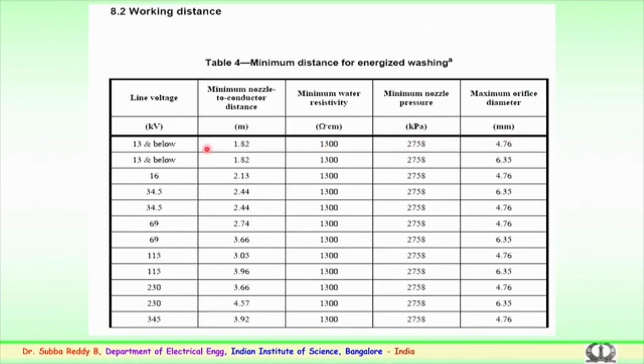So, a few considerations here. In case of 13 kV and below, you can see the minimum nozzle to conductor distance should be maintained at 1.82 meters. The minimum water resistivity is 1300 ohm centimeters. The minimum nozzle pressure to be 2758 kilopascals, and the maximum orifice diameter is 4.76 millimeters.